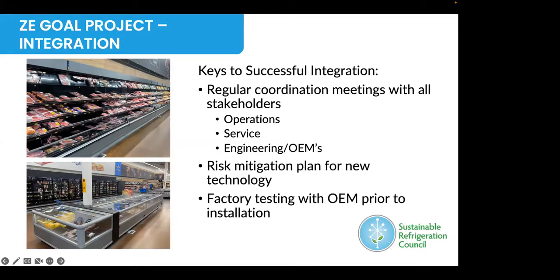And along with that, we did a lot of risk mitigation planning with some backup ideas, or we had a load testing chiller that we put in that could load test the glycol pump skid prior to conversion of all the cases, just to ensure that with the new technology that it would work well and be able to support the loads before we changed out all of the display cases. So some of those things are really the key as to how to integrate these natural solutions without interrupting the store operation.